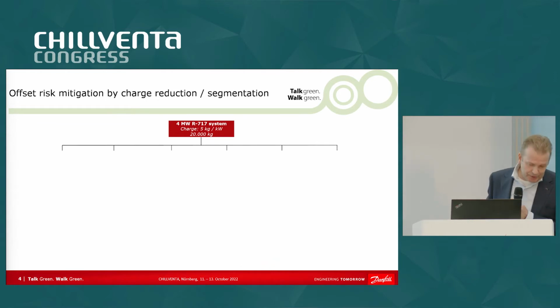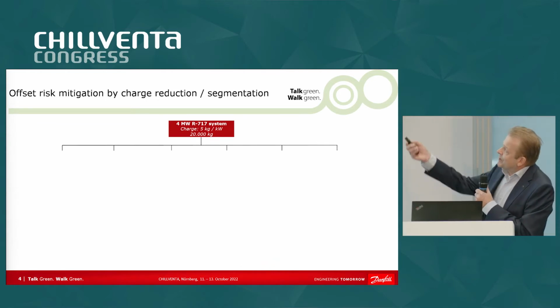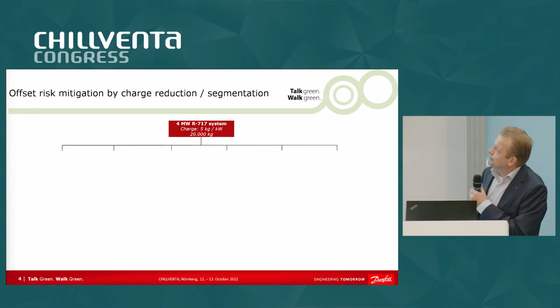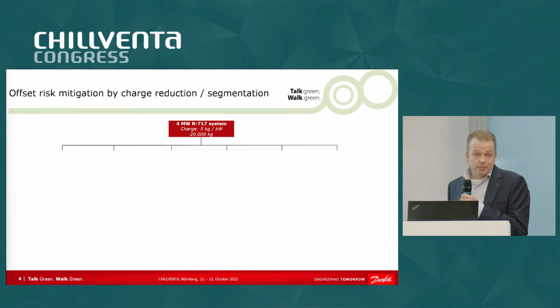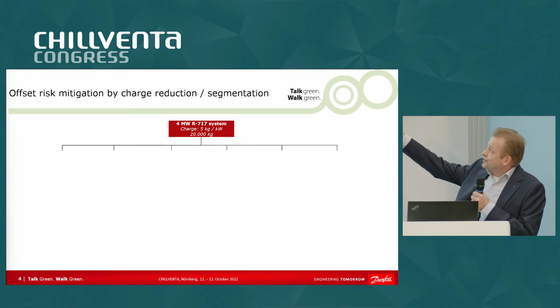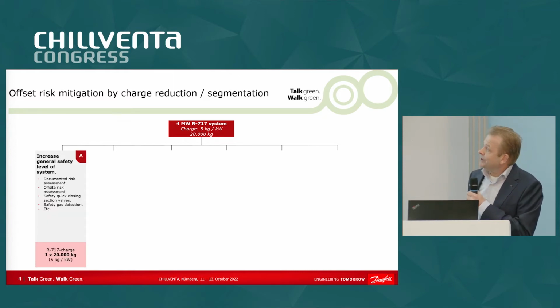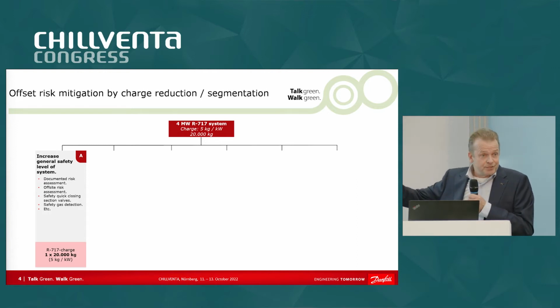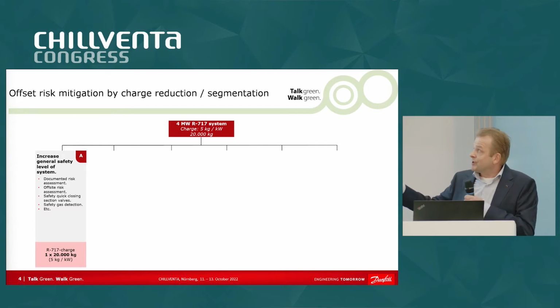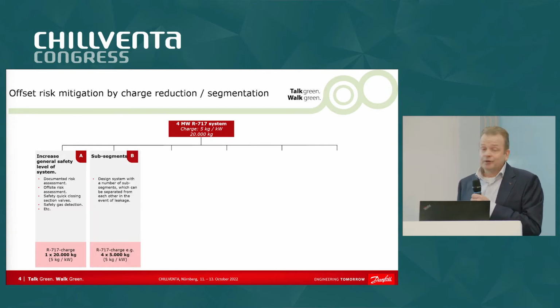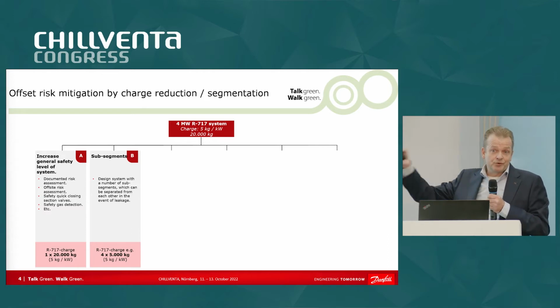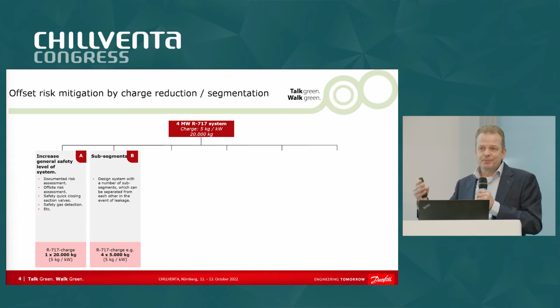So this is an example of, let's say we have an ammonia system in Europe, typical charge, 5 kilogram per kilowatt. So this is a 4 megawatt system, 20,000 kilogram. So if you do nothing, you have one system, one charge, and you just try to make sure that it is as safe as possible. The other thing you could do is split it up. So you split the system in half or in 3, and you mitigate basically the risks of the ammonia systems.